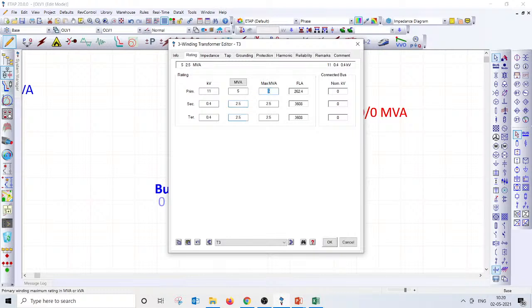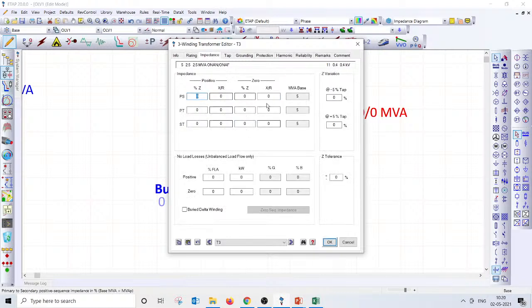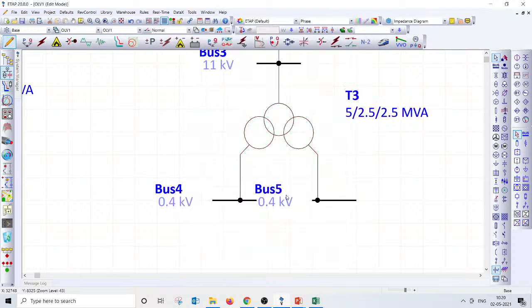So I'm just giving a 3 winding transformer. Here, if you go with a 3 winding transformer, then the typical problem is that you may not have a typical impedance, and it also gives an additional benefit: you have to find out what could be the typical impedance of the transformers, and how to find out the secondary to tertiary impedance is also another story which we can learn.